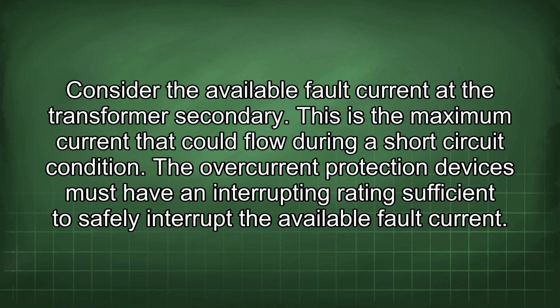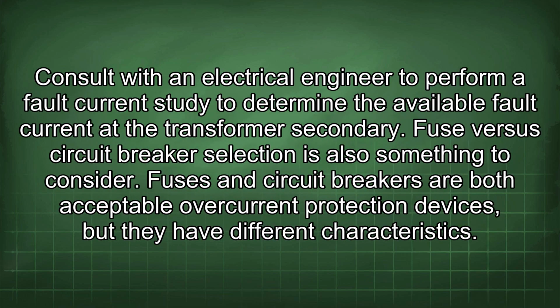Consider the available fault current at the transformer secondary. This is the maximum current that could flow during a short circuit condition. The overcurrent protection devices must have an interrupting rating sufficient to safely interrupt the available fault current. Consult with an electrical engineer to perform a fault current study to determine the available fault current at the transformer secondary. Fuse versus circuit breaker selection is also something to consider.